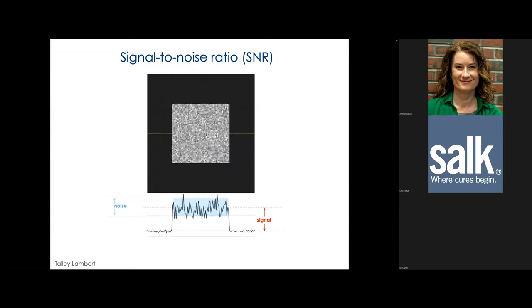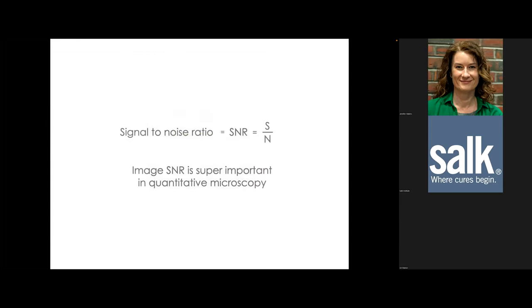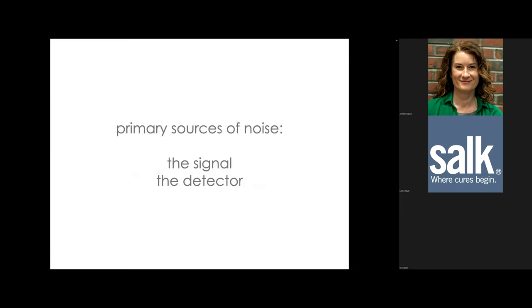There are two primary sources of noise: the signal itself, and noise generated by the detector. When making intensity measurements, you're ultimately counting photons. We often report them in arbitrary units, but the actual unit is photons. Because photon flux is a stochastic process, counting it gives a standard deviation equal to the square root of the number of photons counted — this is Poisson noise, also called shot noise, photon noise, or signal noise.